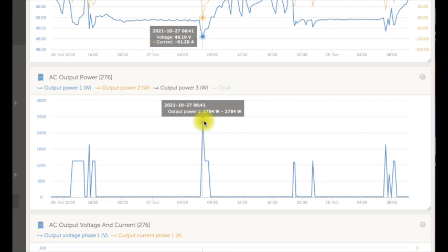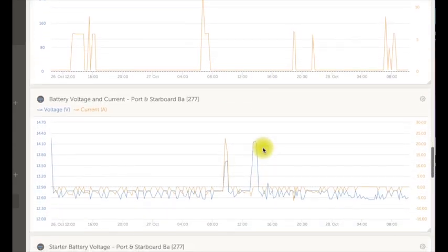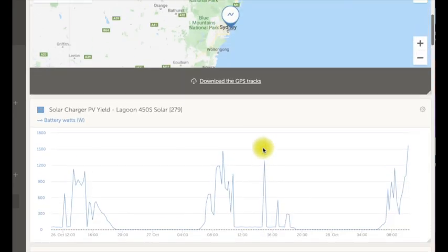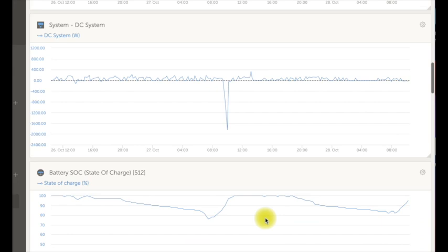Now with Victron inverters, you can do 30% over for 30 minutes. So that's why we tend to say a 5,000 VA inverter is 5,000 watts, because that delta difference between the two you can comfortably do for 30 minutes anyway, 30% over, and you'll get an alert, and then the alert will come off.